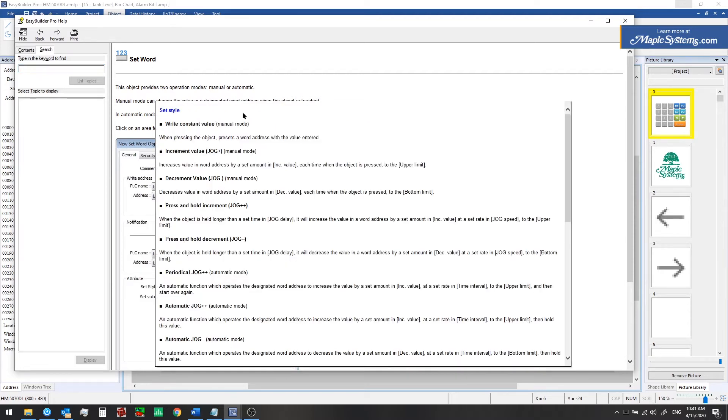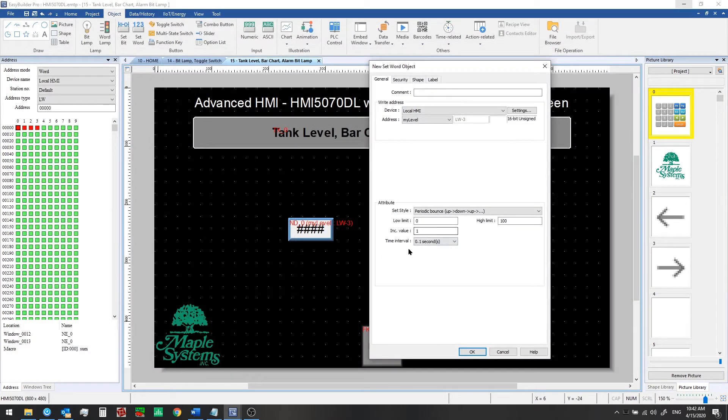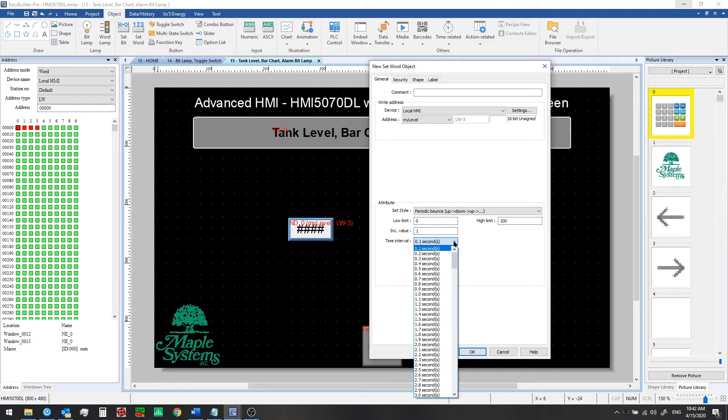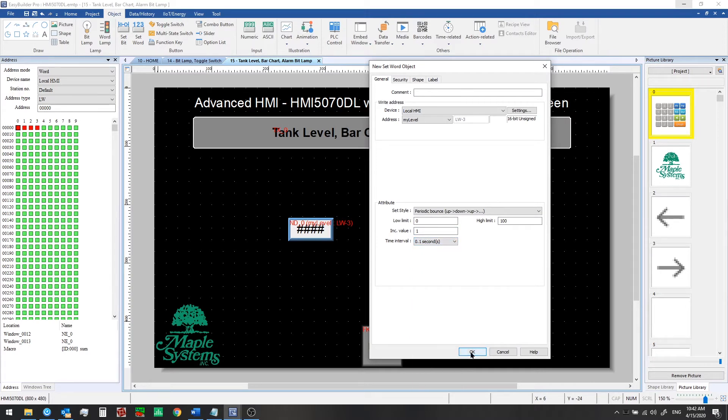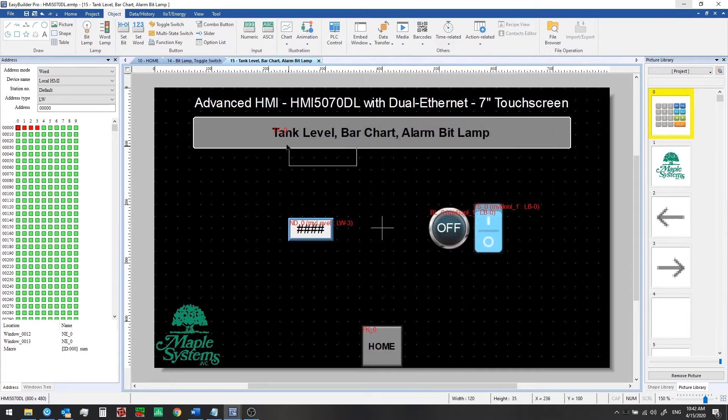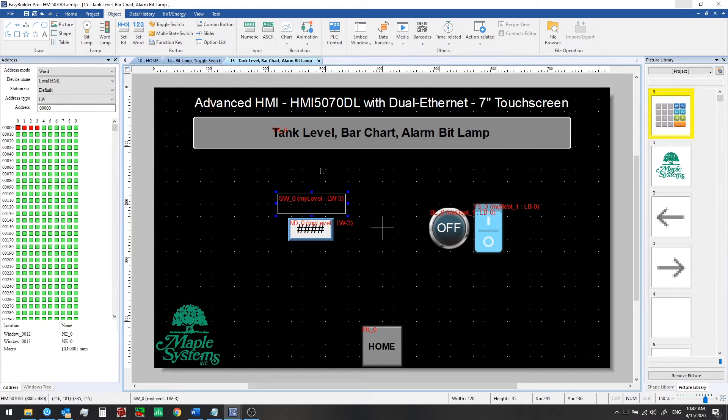So if we click on the set style drop down menu here from the help window it will pull up a full description of all of these features. So we can see that for example periodic bounce uses an upper and lower limit and increment value and a time interval. We'll start from the low go up to the high and come back down. So that's good for now and we'll use low of zero high limit of a hundred increment value of one and the time interval will set to 0.1 seconds. Now we'll click OK and we can place this on the window that will be running as soon as we navigate to this window which will show you in simulation mode in just a moment.